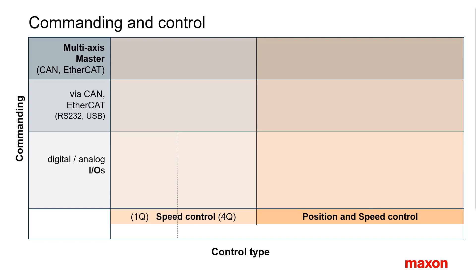Position controllers can usually also be set up as speed controllers. Torque control on motors is equivalent to current control — it is the lowest control level. A controller with a torque control mode may be used as an inner loop in an external speed or position control loop.